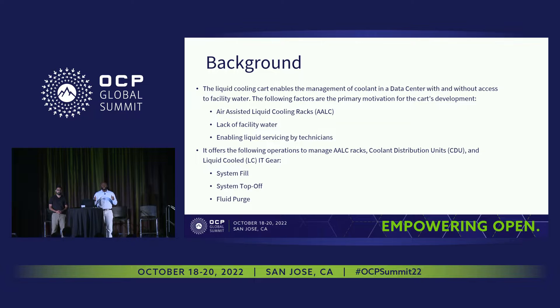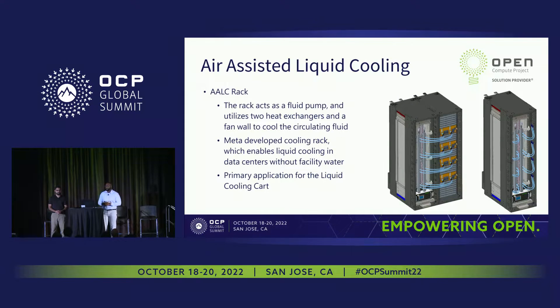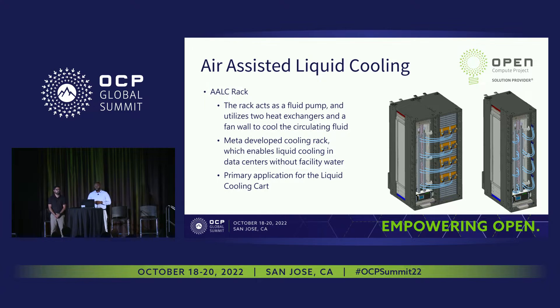We need these different operations whether the AALC rack is entirely empty, whether it needs to have the final amount of fluid or the reserve fluid filled in order to prevent any freezing during transportation, and then finally to drain the rack for servicing. This is a depiction of an AALC rack. On the far right is the AALC rack itself, and on the left is the AALC rack connected to liquid-cooled IT gear. The rack acts as a fluid pump so that it can pump fluid into the gear without the need of facility water, and it is the primary reason that the liquid cooling cart is being designed.